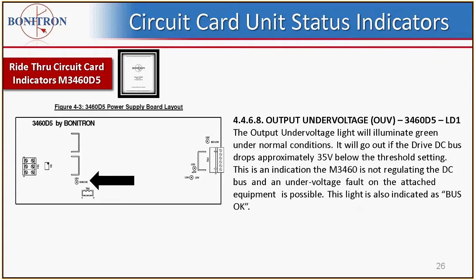Now the power supply board, output under voltage indicator LD1. The output under voltage light will illuminate green under normal conditions. It will go out if the drive DC bus drops approximately 35 volts below the threshold setting.